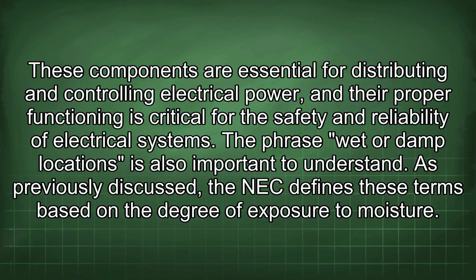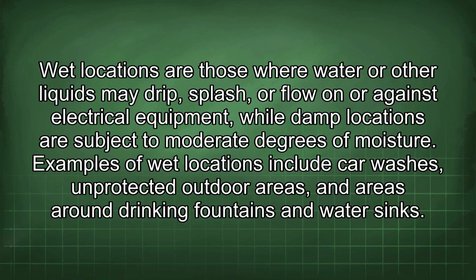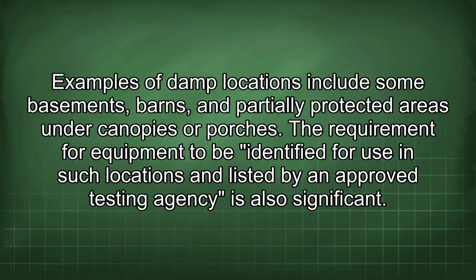reliability of electrical systems. The phrase wet or damp locations is also important to understand. As previously discussed, the NEC defines these terms based on the degree of exposure to moisture. Wet locations are those where water or other liquids may drip, splash, or flow on or against electrical equipment, while damp locations are subject to moderate degrees of moisture. Examples of wet locations include car washes, unprotected outdoor areas, and areas around drinking fountains and water sinks. Examples of damp locations include some basements, barns, and partially protected areas under canopies or porches.